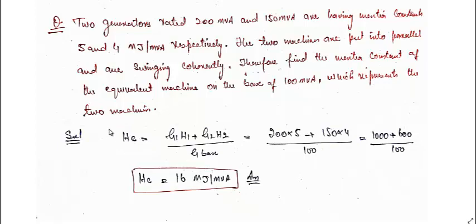So we know that the equivalent inertia constant will be equal to G1 H1 plus G2 H2 divided by G base. What is G1 H1? G1 is 200, H1 is 5, that is 200 into 5. G2 is 150, and H2 is 4, that is 150 into 4, and G base is given to be equal to 100.